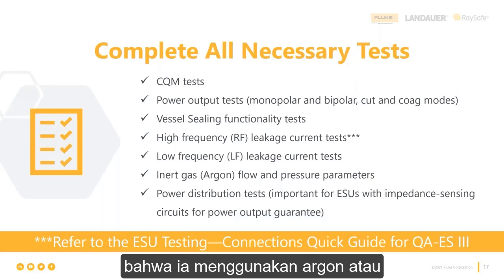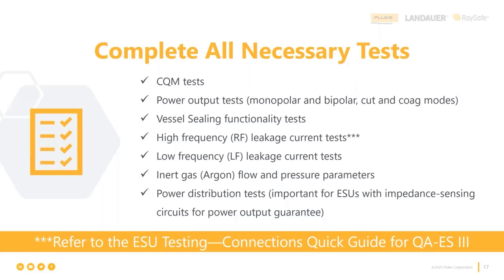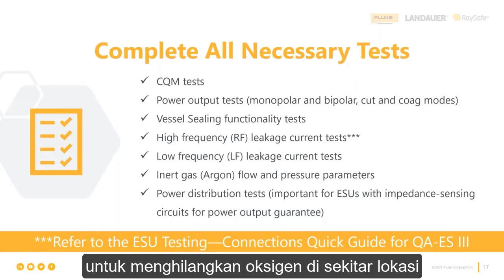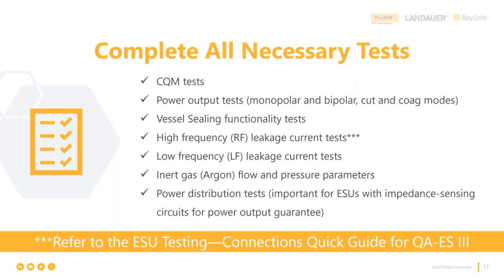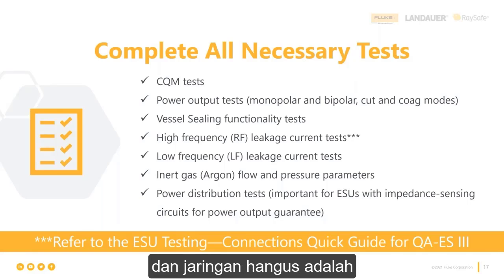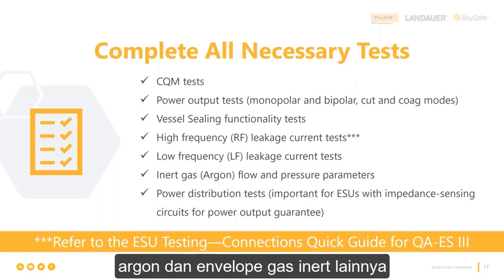Now, another special function in some ESUs is an argon or inert gas envelope that uses argon or some other inert gas to eliminate oxygen around the site of the surgery. And why is that? Well, because oxygen actually causes carbonization. That charring is what you observe, and charred tissue is not clean, straight incision cuts, and they take longer to heal. So the reason for these argon and other inert gas envelopes is to get rid of the oxygen.